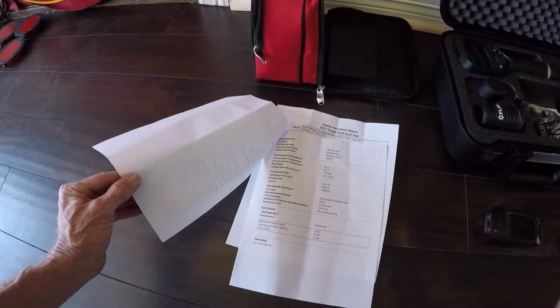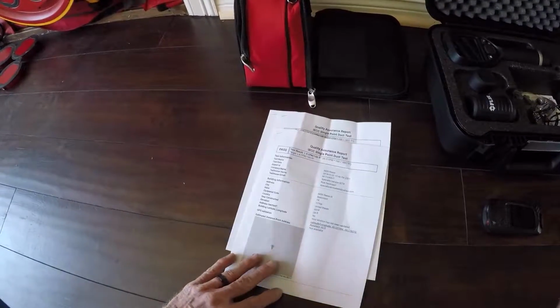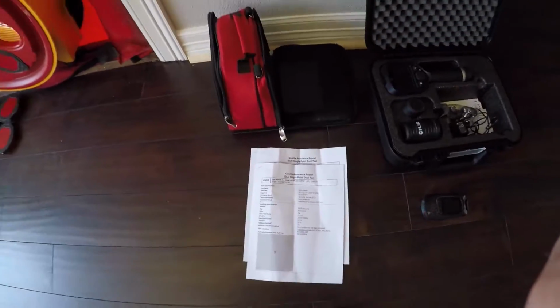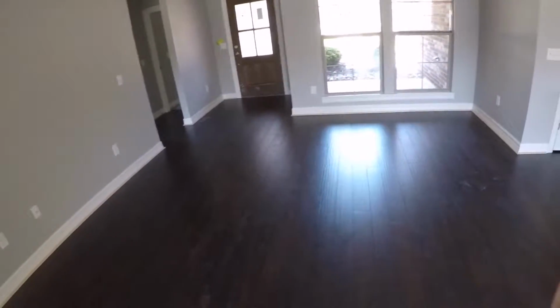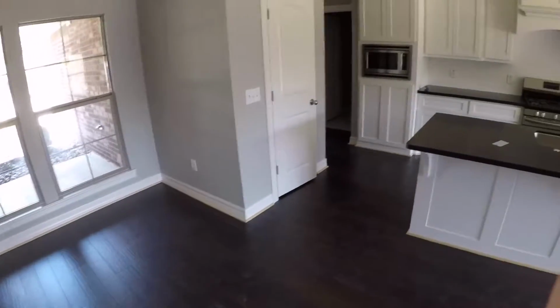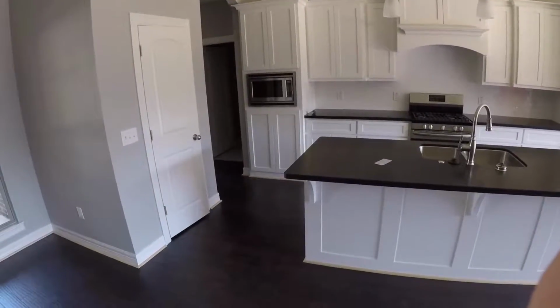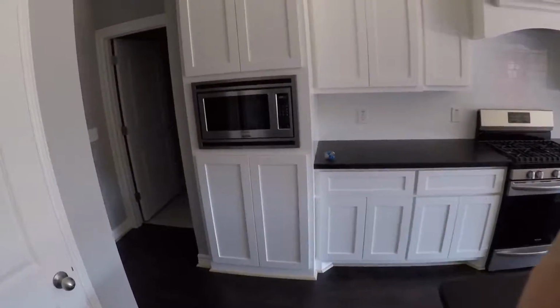we're 1,847 square feet. Now we're basing our duct test off the square footage of the home, and we're looking for 4 CFM of air leakage per 100 square feet. So that being said, the more ductwork, the more chance of leaks. We're all bad about oversizing air conditioners and placing an excessive amount of grills within the homes, which creates the problem where a lot of us are failing the duct test.